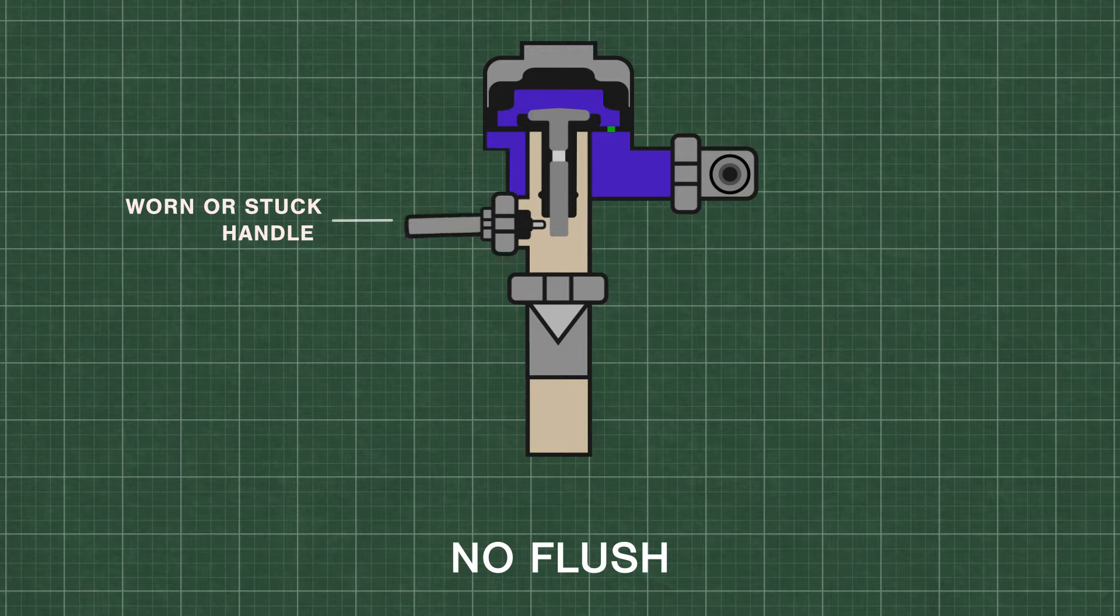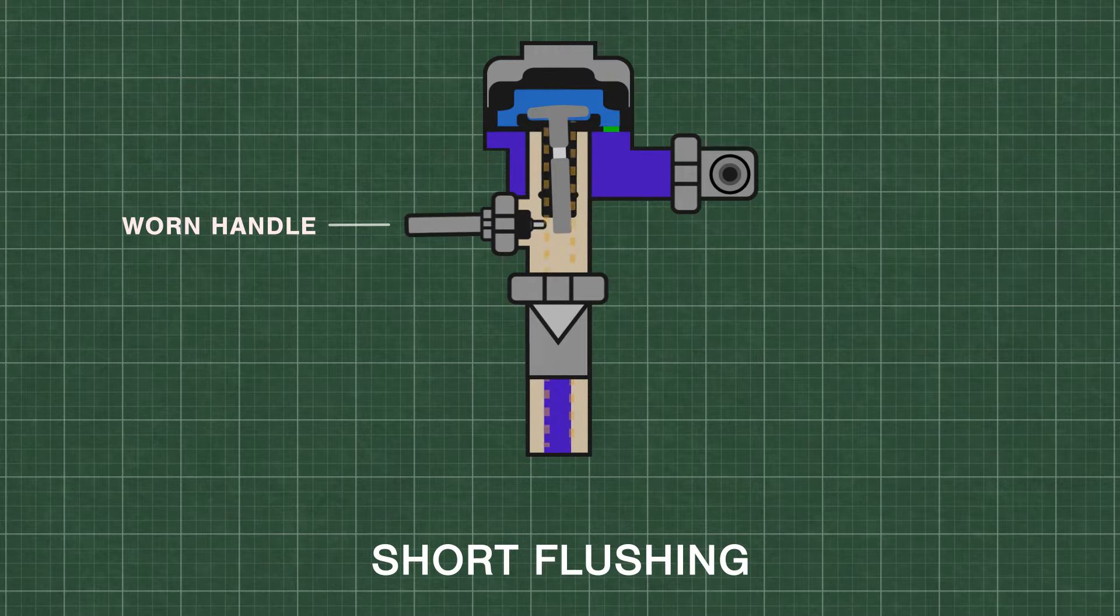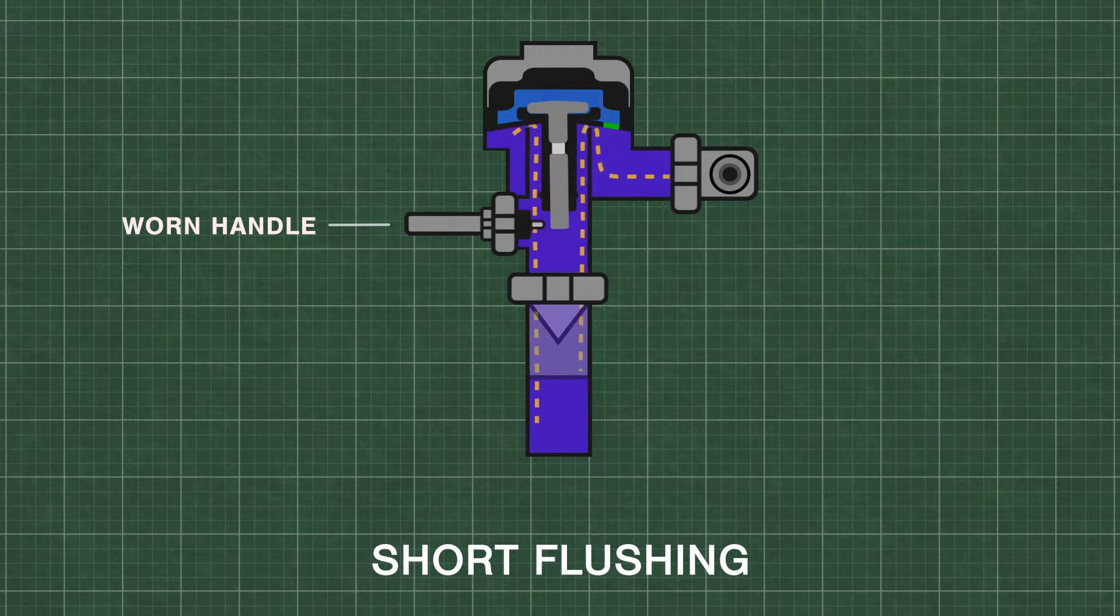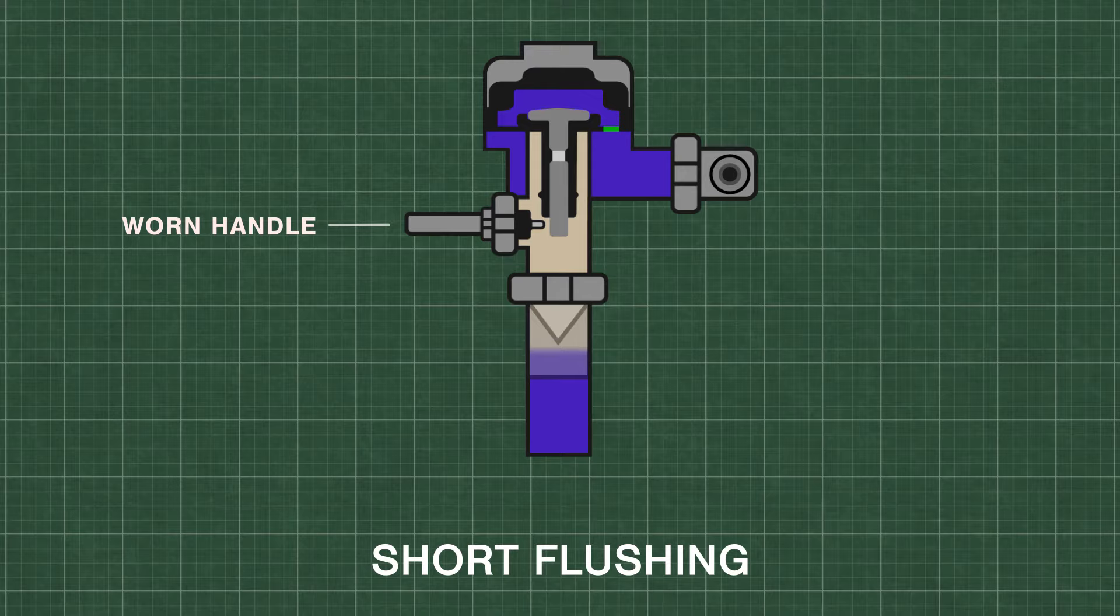If the handle assembly is worn down or starts sticking, the flushometer might not function. Additionally, a worn handle might also cause short flushing if it fails to open the relief valve all the way. You can replace the entire handle or the inside parts.